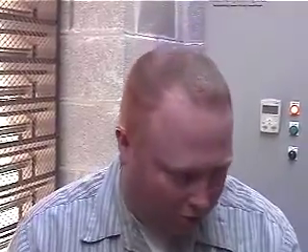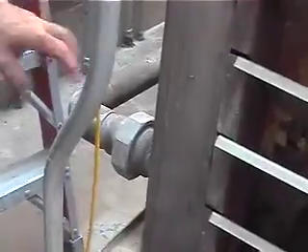If the water gets below 10 inches, I can't remember exactly where, but below where it starts sucking air in, it'll shut the pumps off, and that would require you to manually reset it. We've seen an issue where you shut the pumps off, turn it back on, the water fills back up, and it just goes back and forth, so it will shut down.